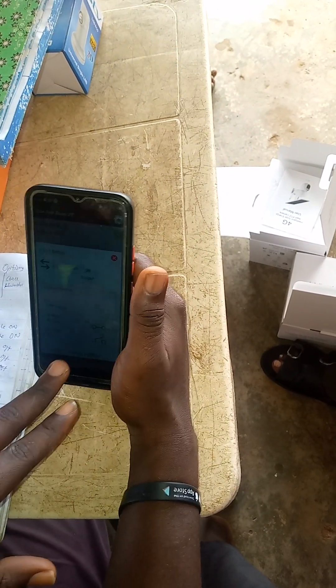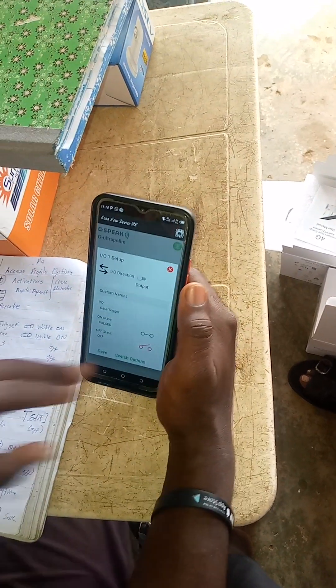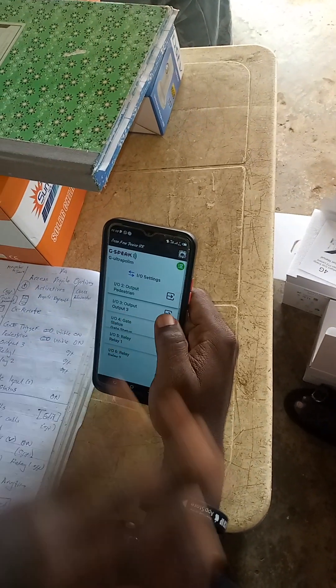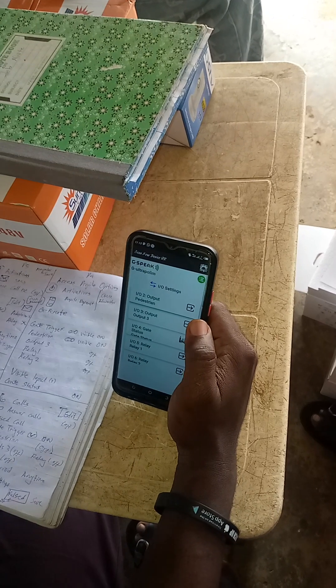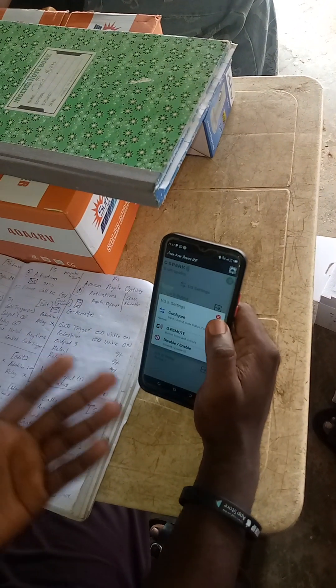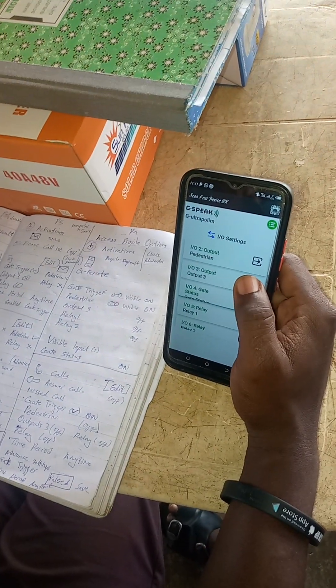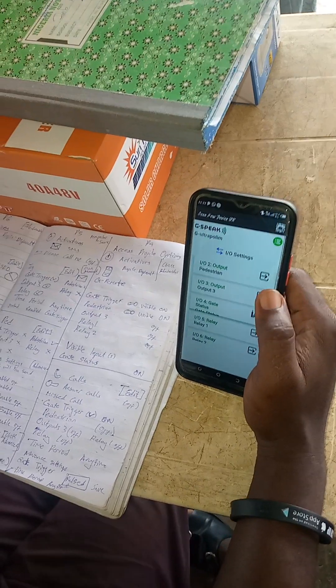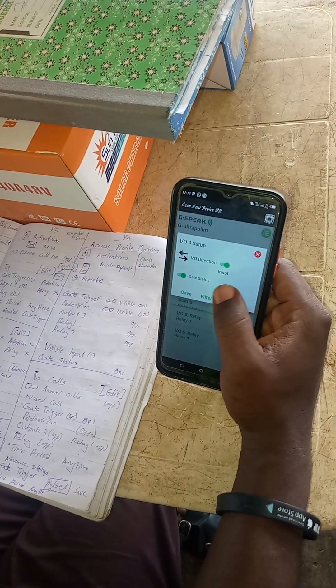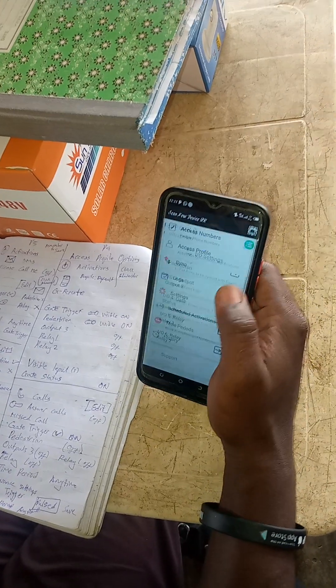It's out. And I want you to set gate on — when you send pulse, open gate; when off, close gate. That's the setting here. For Pedestrian also: is it out or in? Out. Out, open; out, close. Then IO3 — I'm not using IO3 in this setup. I can use IO3 for anti-theft, so that if somebody wants to steal that machine, it should make an alarm. But what we need is status — we want to know the status of the gate. That's IO4. I pick IO4 for my status. Is the gate open or closed? Is it out or in? It's in — input. It will receive response from the gate. I'm not using other IOs. So I'm through with IO mapping now.